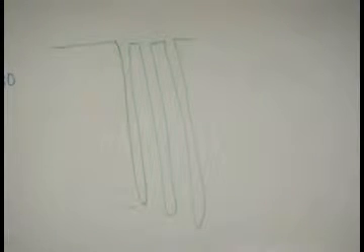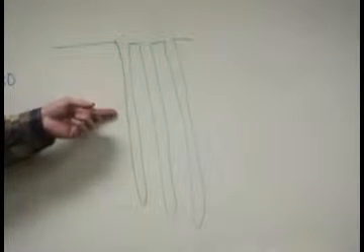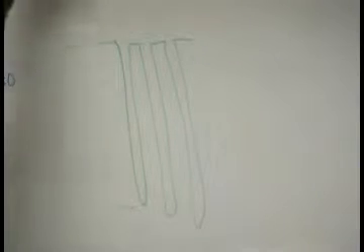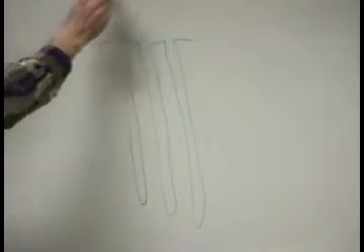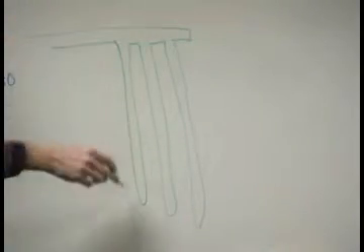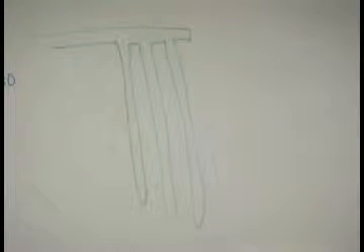LPS, Lincoln Public Schools, does these things a lot. I think the last 2 high schools they built, they put in, I would say, about 200 wells out there, about 15 feet apart. Just make a big grid of them out there on the football field, and pipe those together like this, and the water goes out there, goes through the ground. That ground is a nice, even, hopefully 55 degrees.